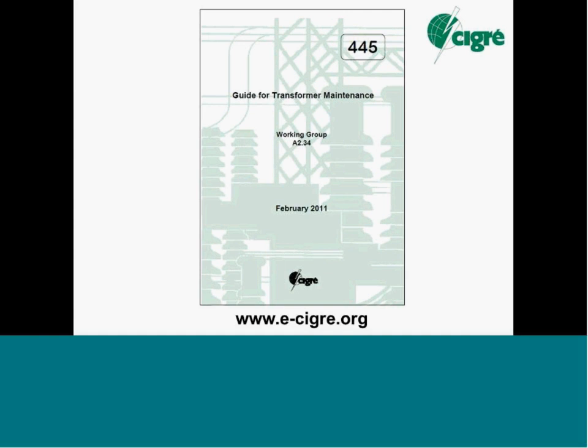We have one question from Michael. He's asked, does the impedance of the transformer change in value over time, or following a high fault current flowing through the winding? A change in impedance would be associated with major movement in the windings or collapse in windings. So you should already see some significant changes in the frequency response as well.